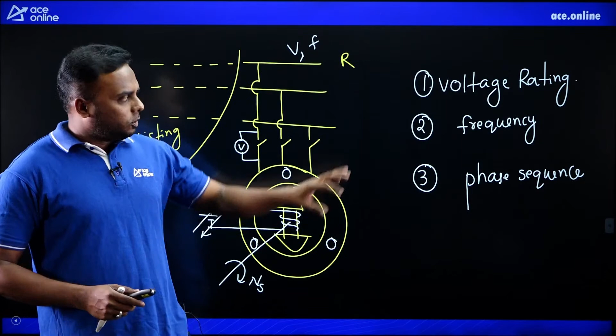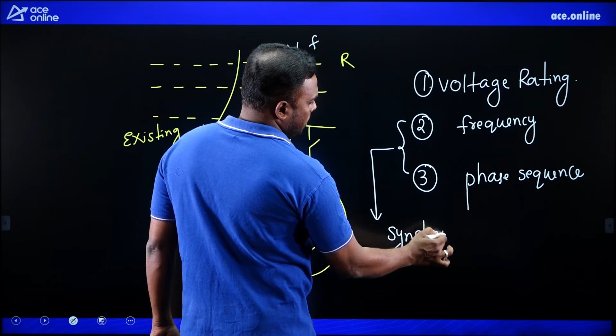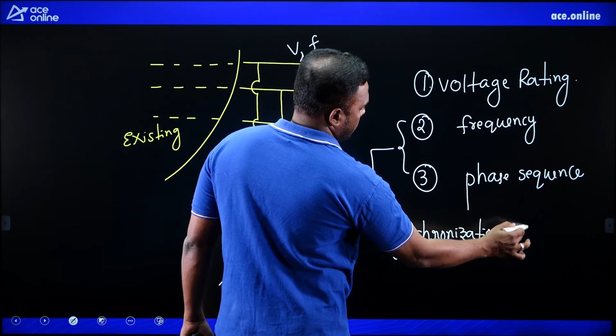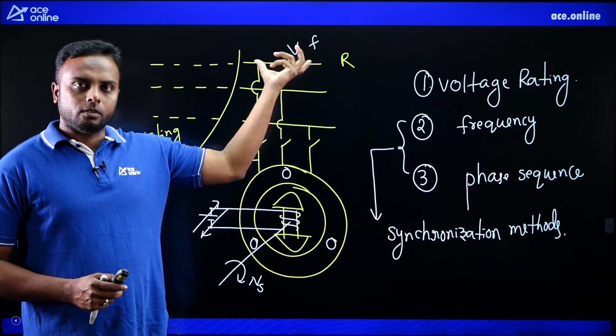These 2 conditions, frequency and phase sequence, we will verify with one of the methods we call synchronization methods. We will see what that synchronization method is, and how we synchronize the alternator with the bus bar. Before that, suppose the frequency of the alternator is not the same as the bus bar frequency. They are different. Then, in order to make both the same, which one do we have to adjust in the alternator? The mechanical input, or steam input, or turbine input. This turbine input we have to adjust, the speed we have to adjust, such that the frequency of both systems is the same.